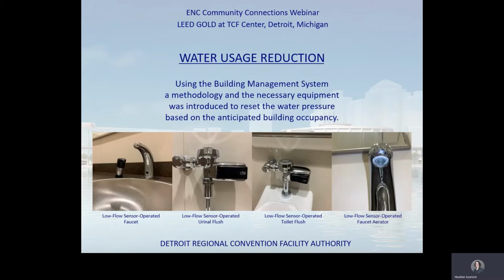This monitoring was used for several energy reduction strategies. The necessary equipment was installed and connected to the building management system to reset the building water pressure based on the building's occupancy.